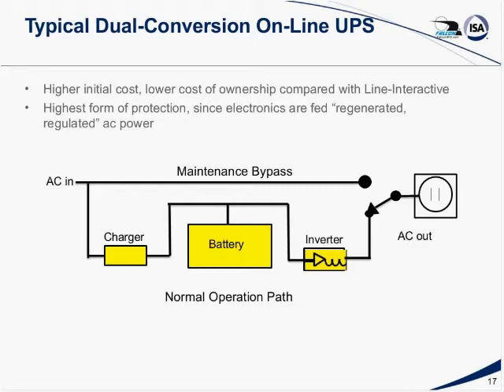The online UPS converts the incoming AC to DC, which removes pretty much most of the power pollution problems. Frequency problems go away. The surge and transients are eliminated. Sags and swells go away.